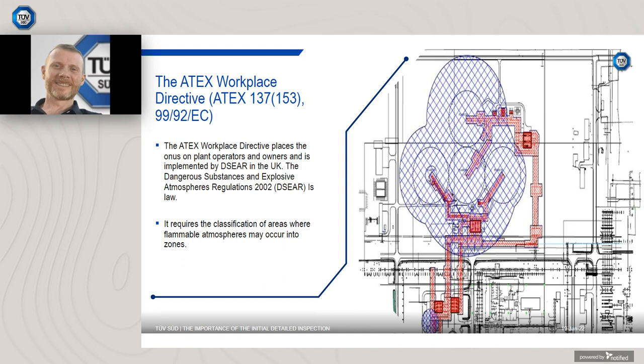The ATEX Workplace Directive, ATEX 153. The ATEX User Directive and the Chemical Agents Directive 98/24 form together to make DSEAR. The ATEX Workplace Directive places the onus on the plant operators and owners and is implemented by DSEAR in the UK. The Dangerous Substances and Explosive Atmospheres Regulations 2002, DSEAR, is law. It requires the classification of areas where flammable atmospheres may occur into zones.